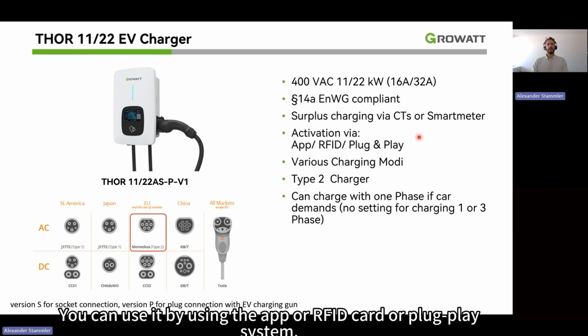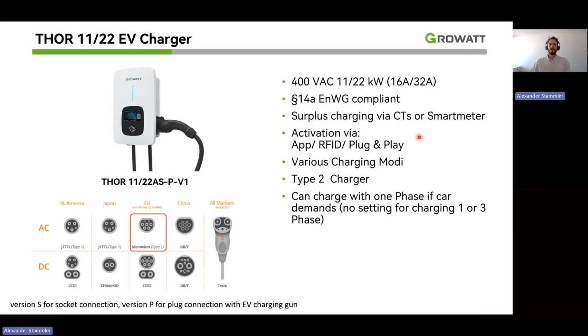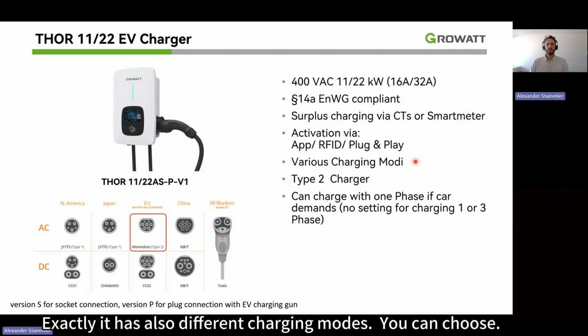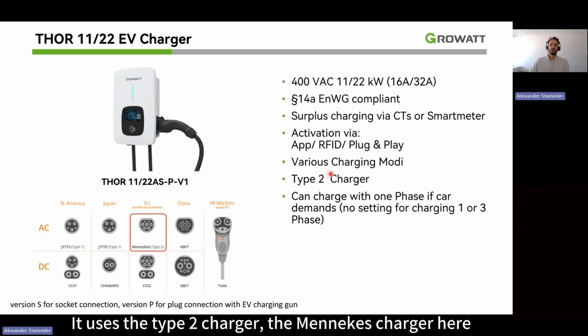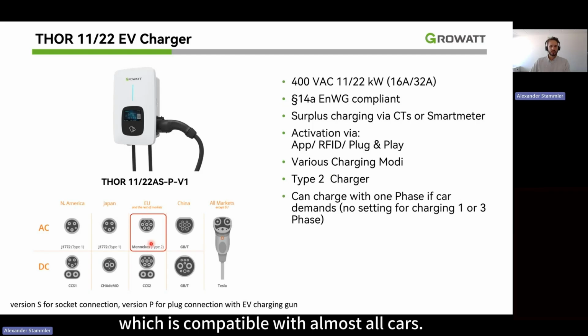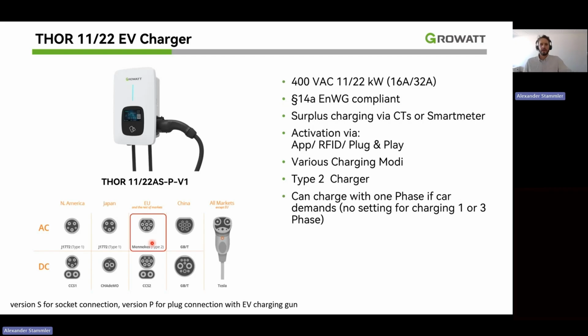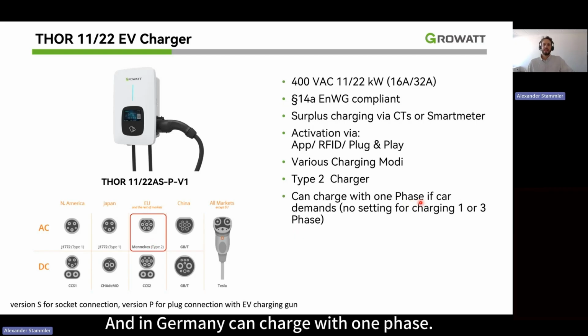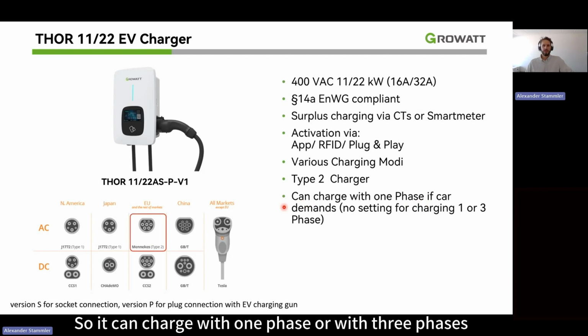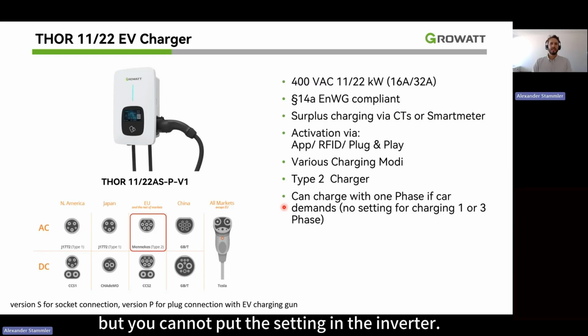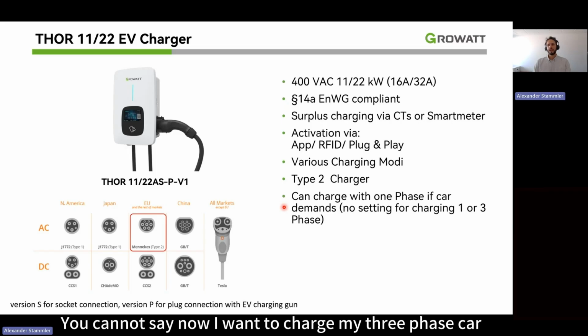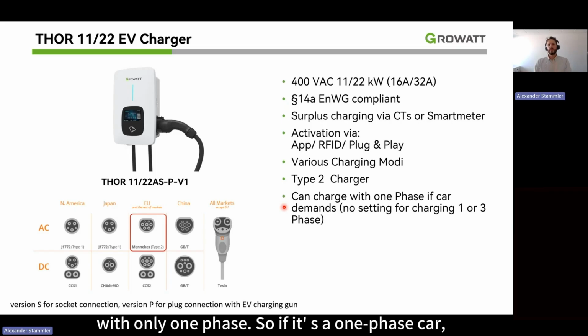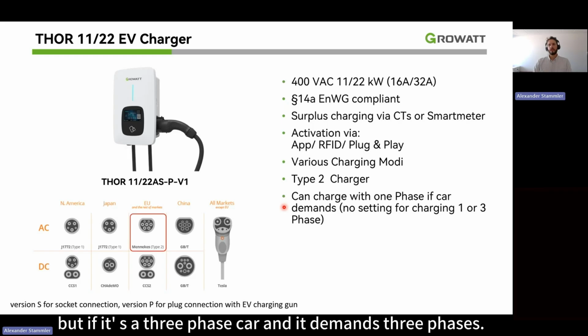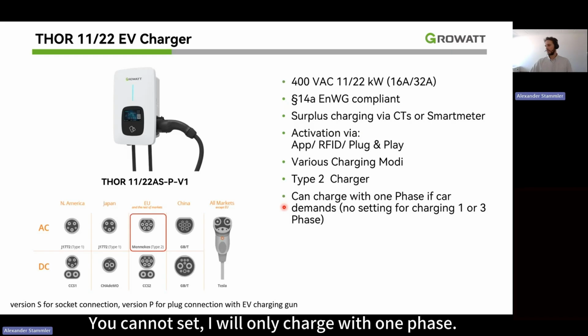You can use it by using the app or RFID card or plug and play system. Exactly, it also has different charging modes you can choose from. It uses the Type 2 charger, the Mennekes charger, which is compatible with almost all cars, I think, in Germany. It can charge with one phase or with three phases, but you cannot put the setting in the inverter. You cannot say, now I want to charge my three-phase car with only one phase. That's exactly right. If it's a one-phase car, it will only use one phase. But if it's a three-phase car and it demands three phases, you cannot set it to only charge with one phase.